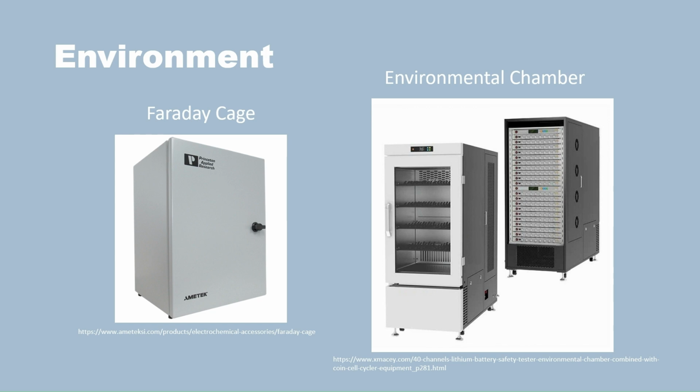So just another thing to consider for your environment, maybe if you're working with really small currents or potentials, you might want to consider a Faraday cage to prevent getting contamination from your fluorescent lights or all the noise that you get from all the electrical equipment in the laboratory. Not always super important, but if you're working with very small currents and potentials that are very sensitive, then you might want to consider a Faraday cage.